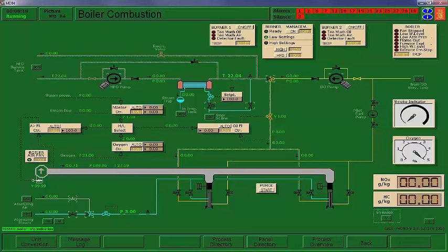We've done our purge. Now, go ahead and bring your damper down to about 9%. And then watch your damper drop down here. By the way, this will not go below 3%. It will never close the dampers all the way, to try to maintain a fire. Your firing rate will be set initially at 15%.